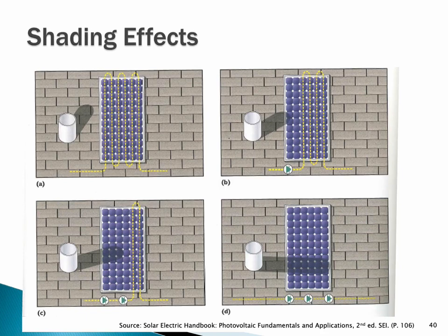When the sun starts shading the side of the module, we lose that cell group. And so these things called bypass diodes block off this cell group and reroute electrons around it. So it's like a detour. And so the module is still functioning, but it's lost 1/3 of its voltage output.